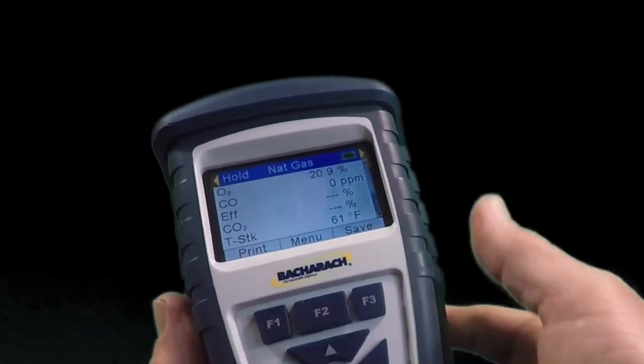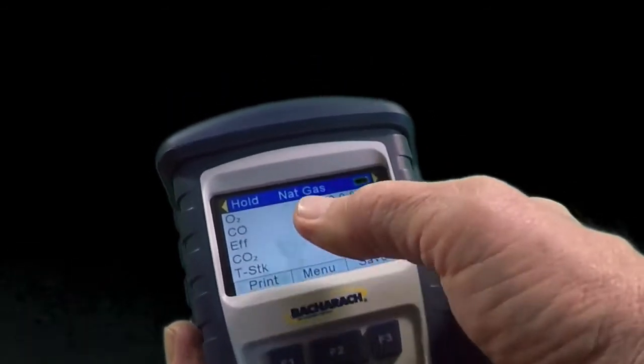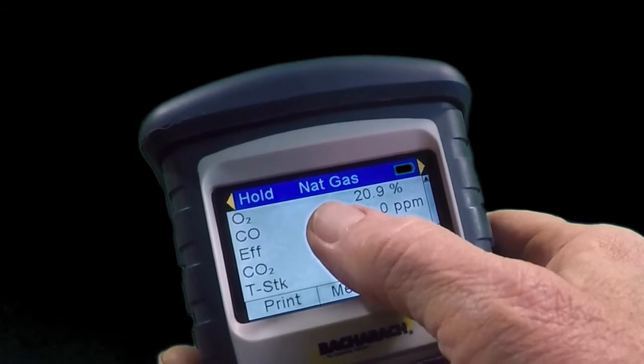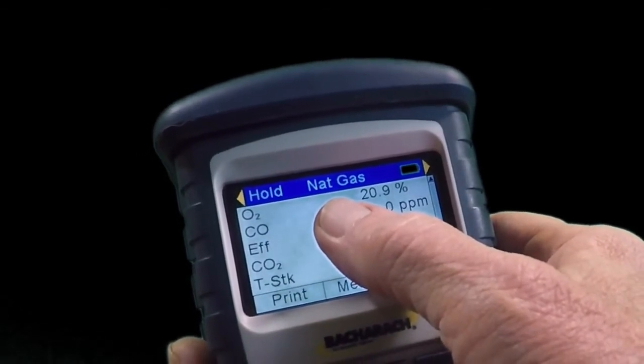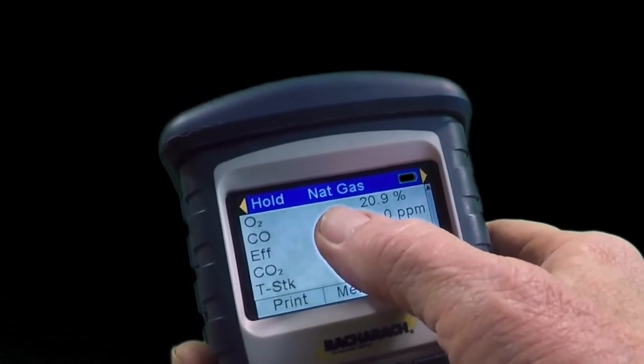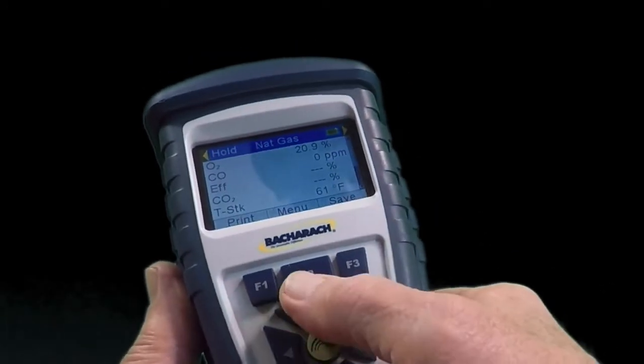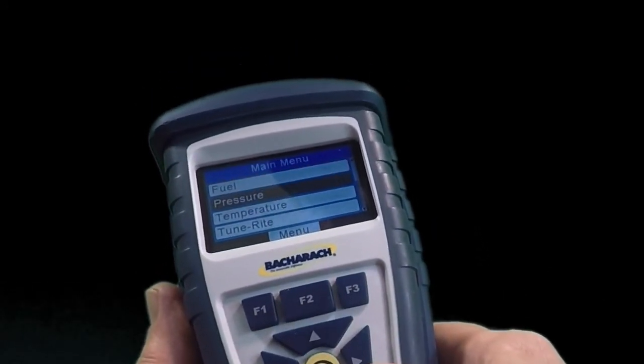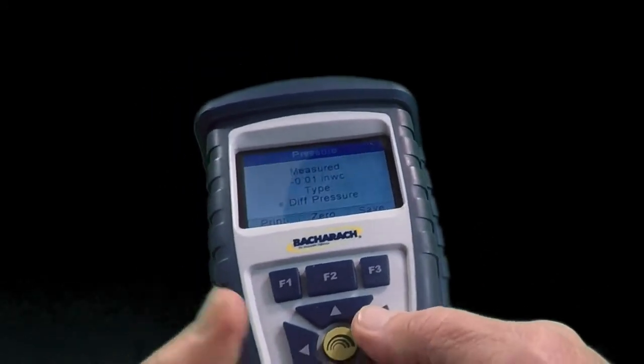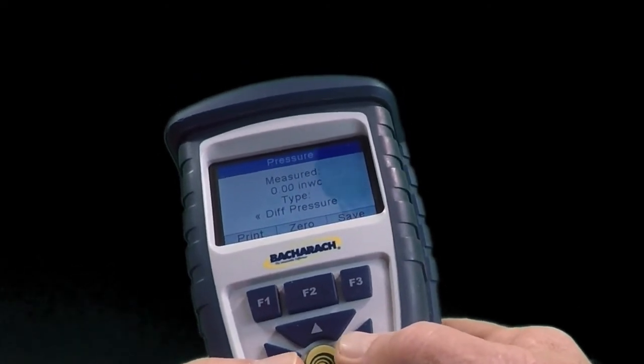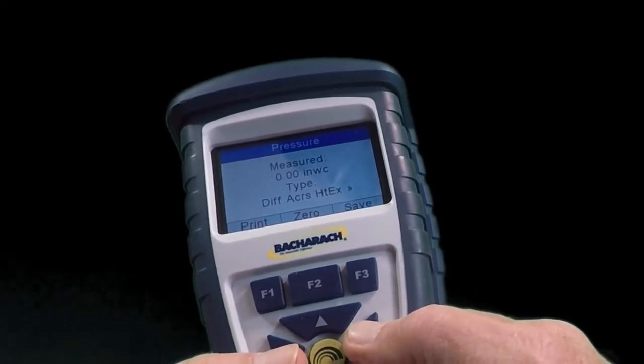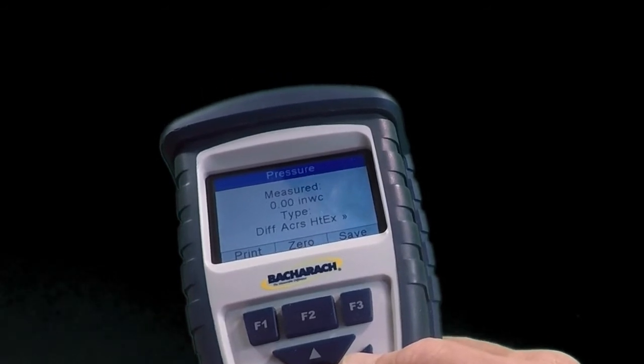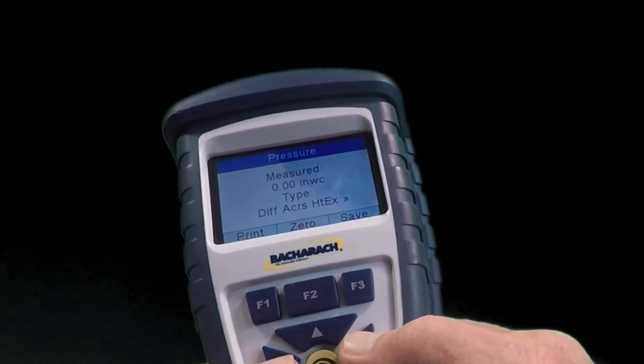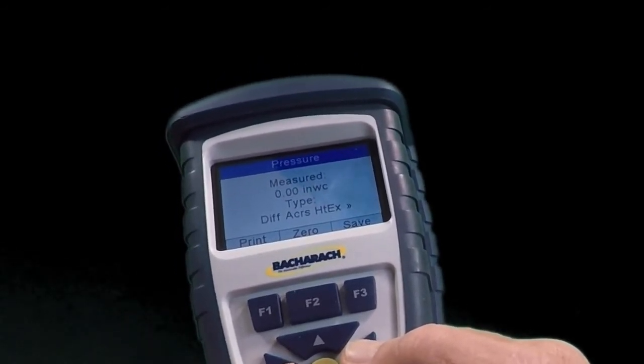So we're back to the display screen. You'll notice at the top it says natural gas. That's the fuel we've selected. That's really important for those calculated readings. Then we'll go back to the menu button. We'll hit pressure. We'll go to the pressure reading. I can scroll right or left to do the different types of pressure readings. You can do differential pressure, draft, or just simply a pressure reading, whatever.